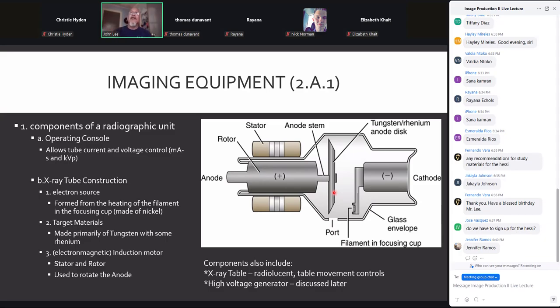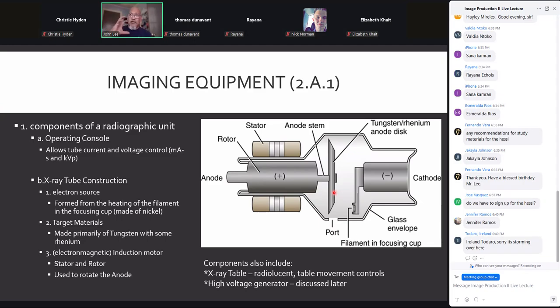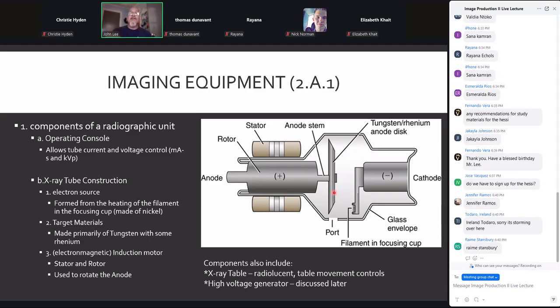Now, graphite is used because we are having this large, heavy device that's going to spin at a very, very high rate of speed. Remember, for single phase through 3-phase generators, you're looking at about 3,400 RPM. For a high frequency generator, the anode spins at about 10,000 RPM. Now, because of those high rates of rotation, just like a wheel and tire assembly on your car, that needs to be balanced. And one of the things that they utilize for that is graphite when they produce those discs, because graphite is very malleable and you can take little bits of it out to help balance the disc so that it doesn't wear the bearings in the rotor end.